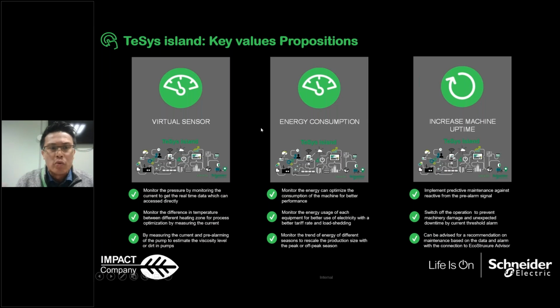You don't need an actual sensor installed in the motor. Let's say for very legacy installations at the site, basically they do not have PT100 temperature sensors installed in the motors. But with this island, even though it's difficult to install a temperature sensor or retrofit the motor installations, you can still use the TeSys Island, monitoring the current to estimate the change of the temperature of the motors. This is what we call the virtual sensors, because we have analog modules and digital modules, so you can input all the sensor signals to the system.